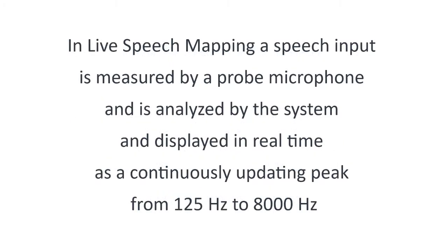In live speech mapping, a speech input is measured by a probe microphone and is analyzed by the system and displayed in real-time as a continuously updating peak from 125 Hertz to 8,000 Hertz.